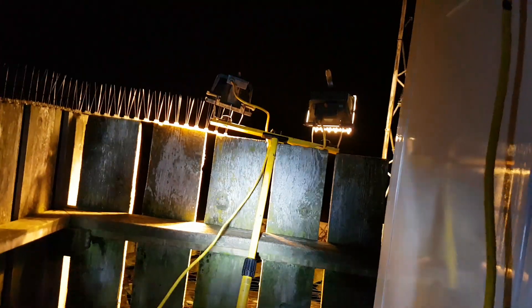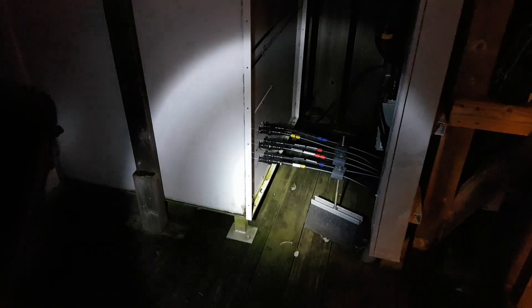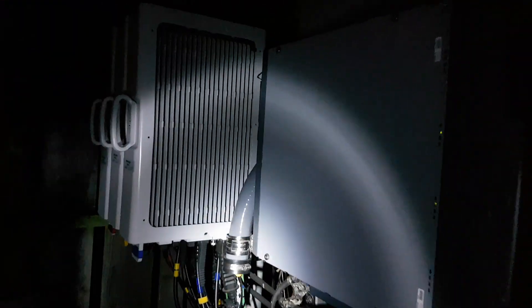We set up a light because we're going to have to put a lockout grounding on the base of that tower. Even though it's turned off, there might be some residual power or induction from other areas. Inside this box where the light is shining is where all the cables come out — this is an induction box. It reduces all the electricity coming off that tower, which is powered, before those cables bring the power to the radios here. We don't want to fry those radios.